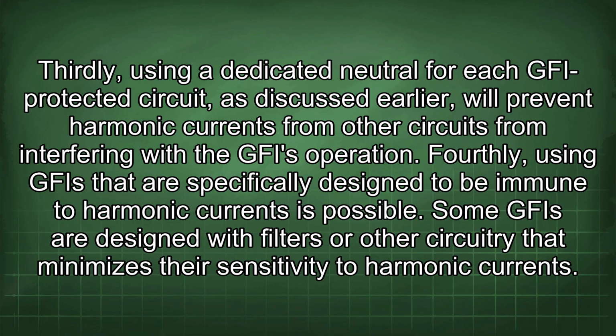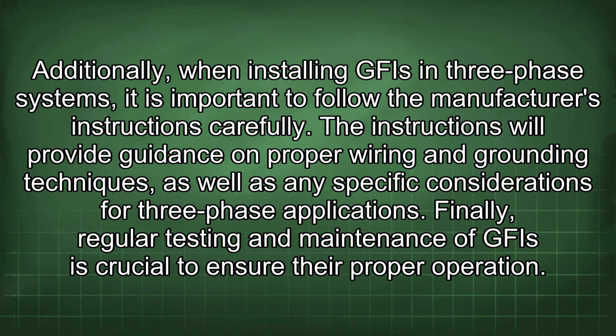Thirdly, using a dedicated neutral for each GFI protected circuit, as discussed earlier, will prevent harmonic currents from other circuits from interfering with the GFI operation. Fourthly, using GFI that are specifically designed to be immune to harmonic currents is possible. Some GFI are designed with filters or other circuitry that minimizes their sensitivity to harmonic currents. Additionally, when installing GFI in three-phase systems, it is important to follow the manufacturer's instructions carefully. The instructions will provide guidance on proper wiring and grounding techniques, as well as any specific considerations for three-phase applications.